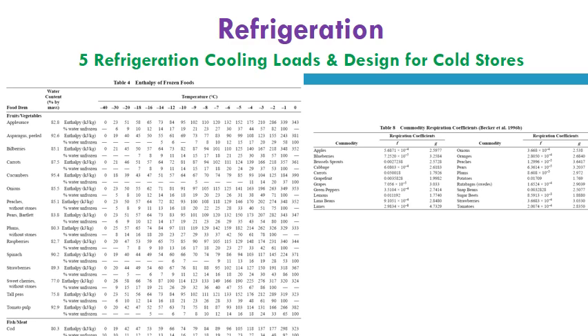Continuing, table 4 gives the enthalpy of freezing food at different temperatures, and the commodity respiration coefficients by Becker for different types of fruits and vegetables, such as apple, are listed here: F is the respiration factor, and G is the second coefficient, which should be used in the respiration load calculation for fresh fruits and fresh vegetables. Both tables, table 4 and table 8, are from chapter 8 of the ASHRAE Refrigeration Handbook.